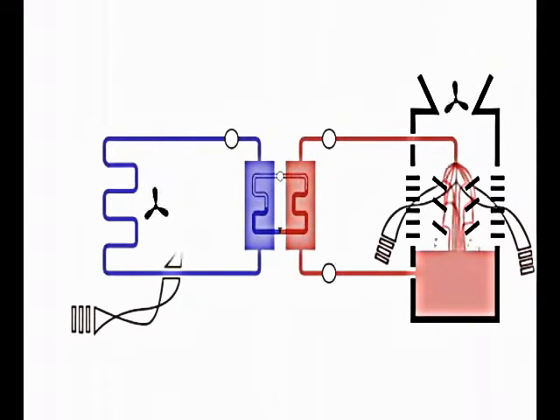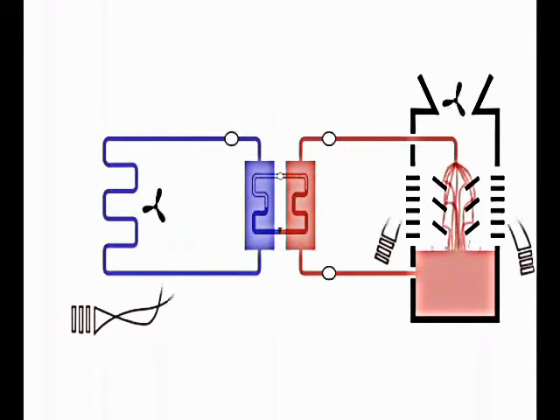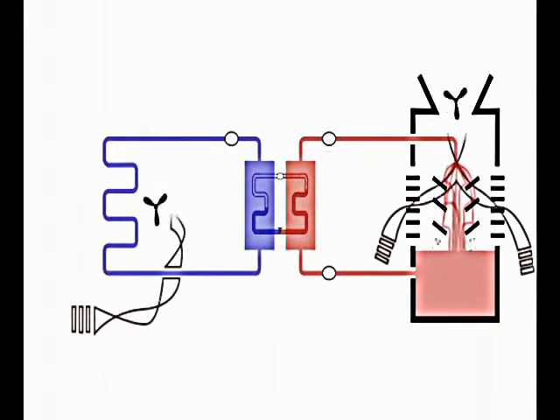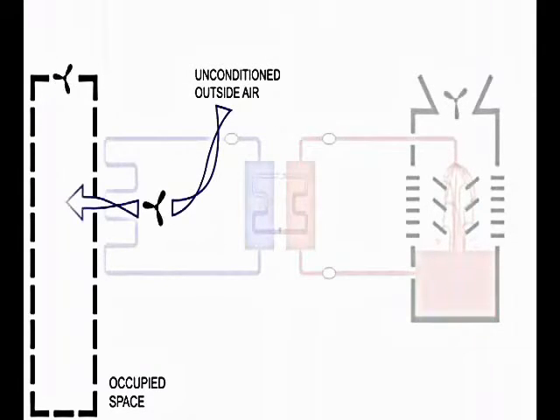Now, what you just saw is called a water side economizer because it relies on cold air to chill water. Like a water side economizer, an air side economizer uses the cold outside air to bypass traditional air conditioning in an effort to save energy. Why air condition when it's cold outside? In this case, in the air side economizer, it may be more energy efficient to directly introduce cold outdoor air to the inside so your equipment doesn't have to mechanically cool the warmer recirculated air. As a side benefit, this offers superior indoor air quality. All that fresh air replaces what would otherwise be mostly recirculated air.